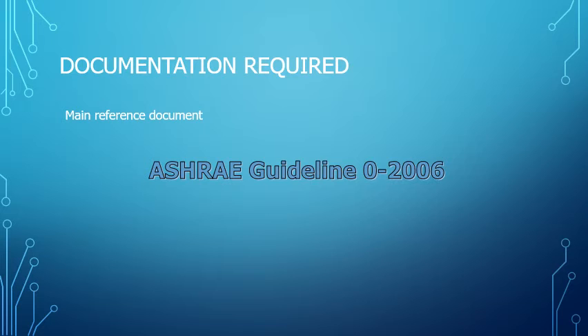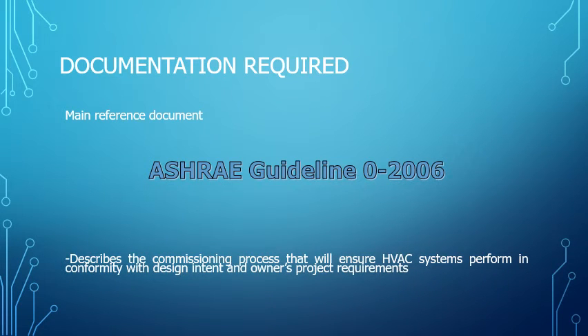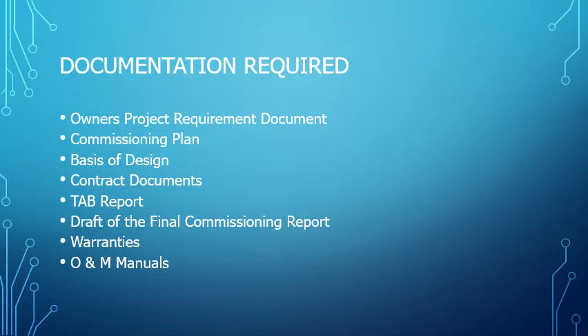So what is the documentation required? Usually for our case, for the HVAC system, we are referring to the ASHRAE guideline. The ASHRAE guideline has its own specification. The documentation that is required is the owner's project requirement document, the commissioning plan, the basis of design, the contract documents, the TAB report or testing air balancing report, the draft and final commissioning report, the warranties, and the operation and maintenance manual.